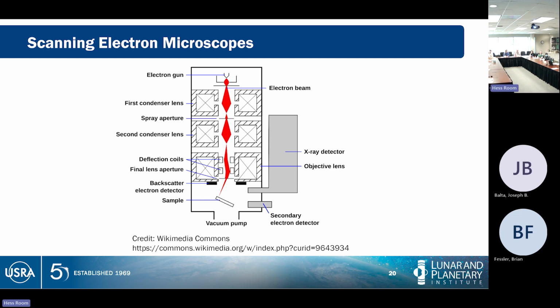licensed images. The structure of an SEM starts with an electron gun. We start off at the top generating free electrons. We send those electrons down a column past a series of lenses and apertures until they hit our sample. When they hit our sample, there are a set of interactions that take place between solid matter and an electron beam that set off responses that can be detected by the right type of detector.